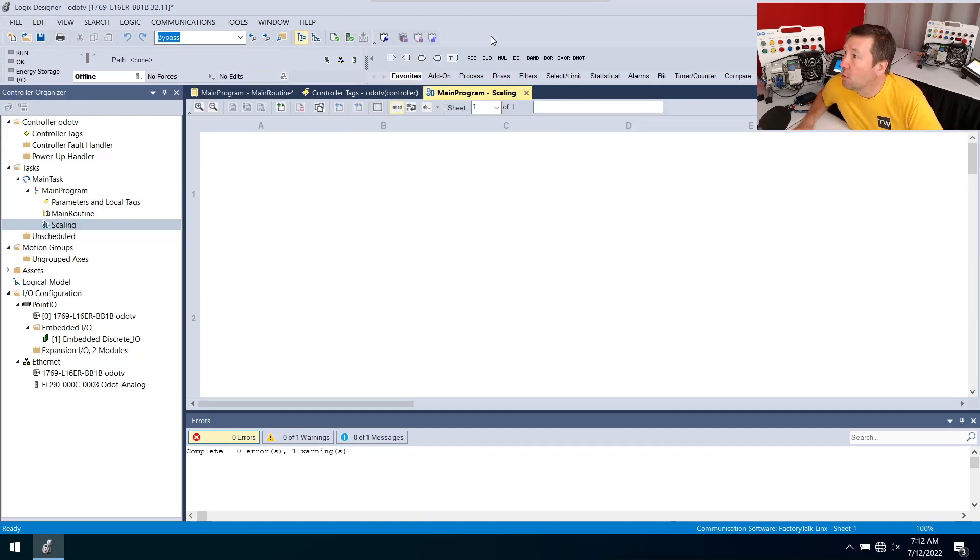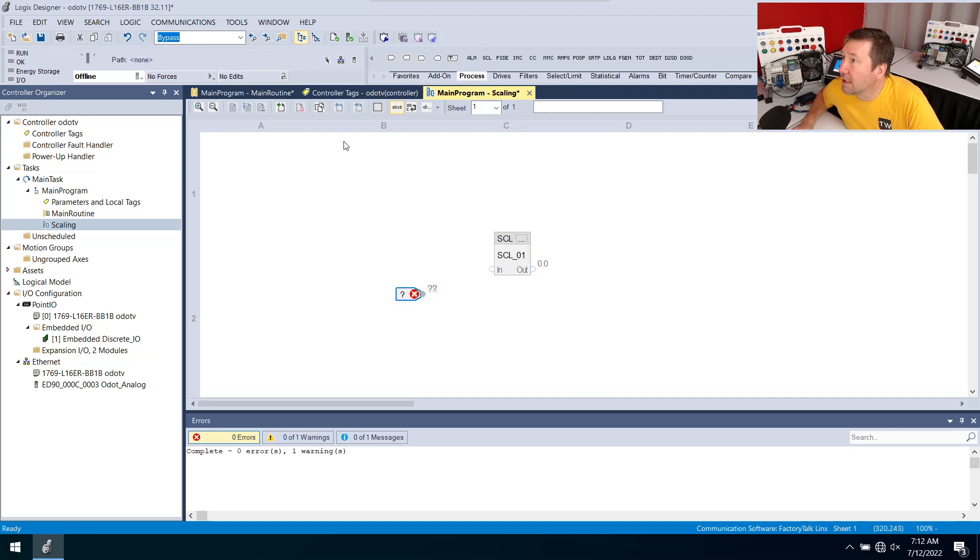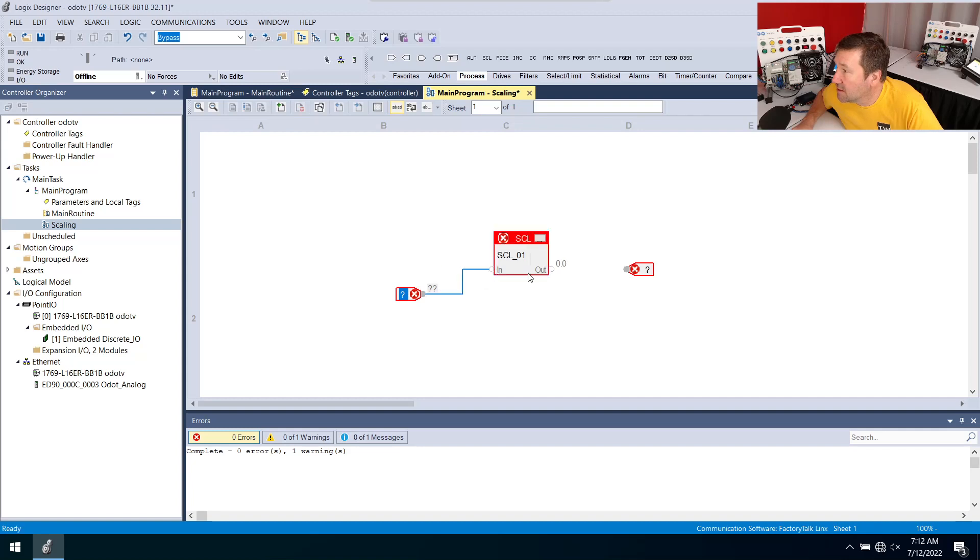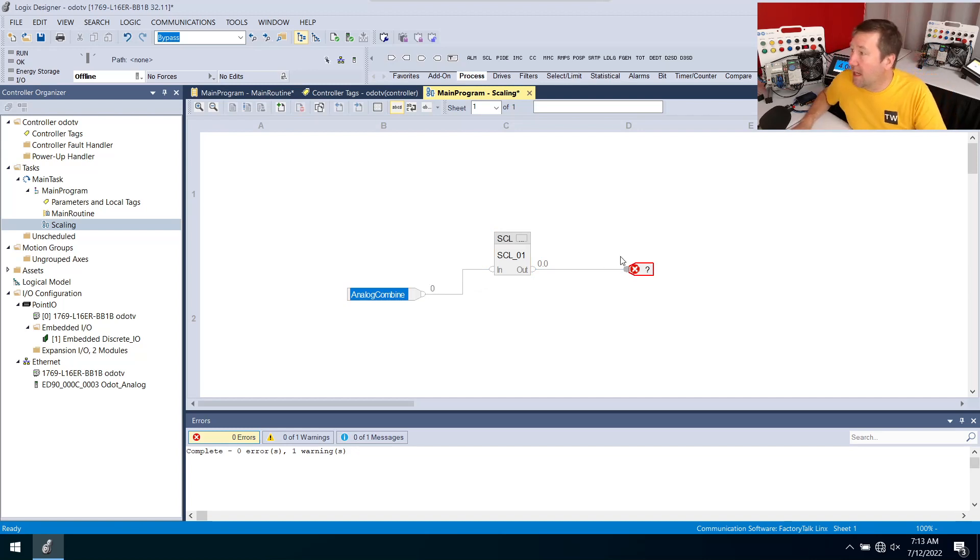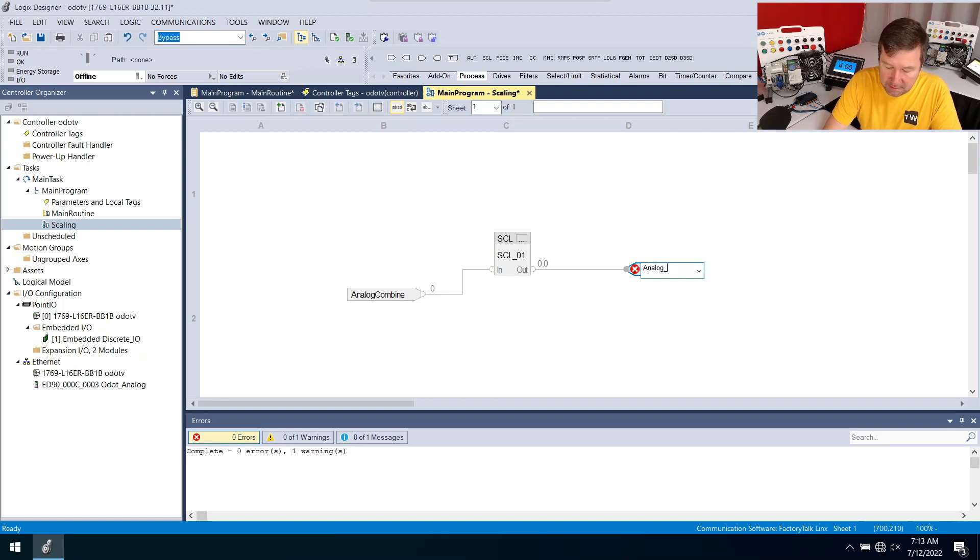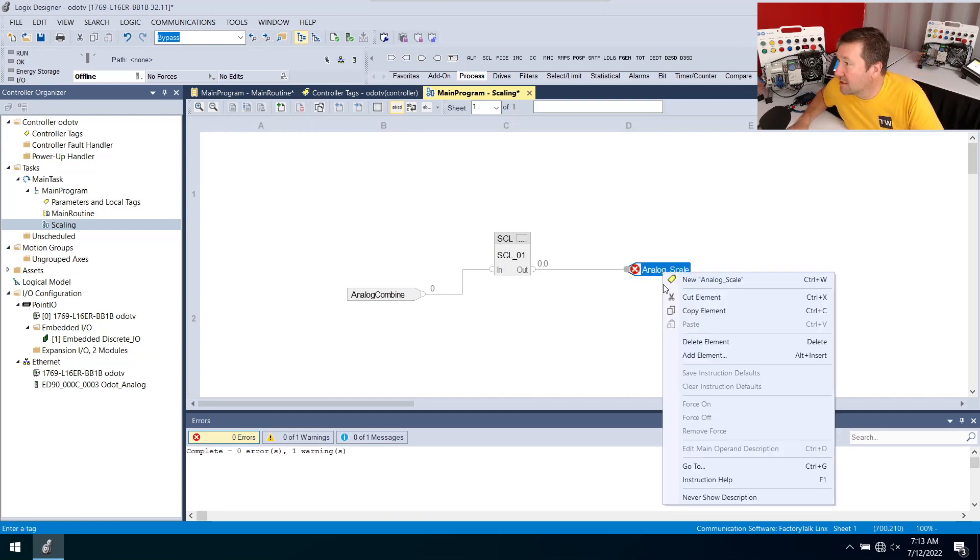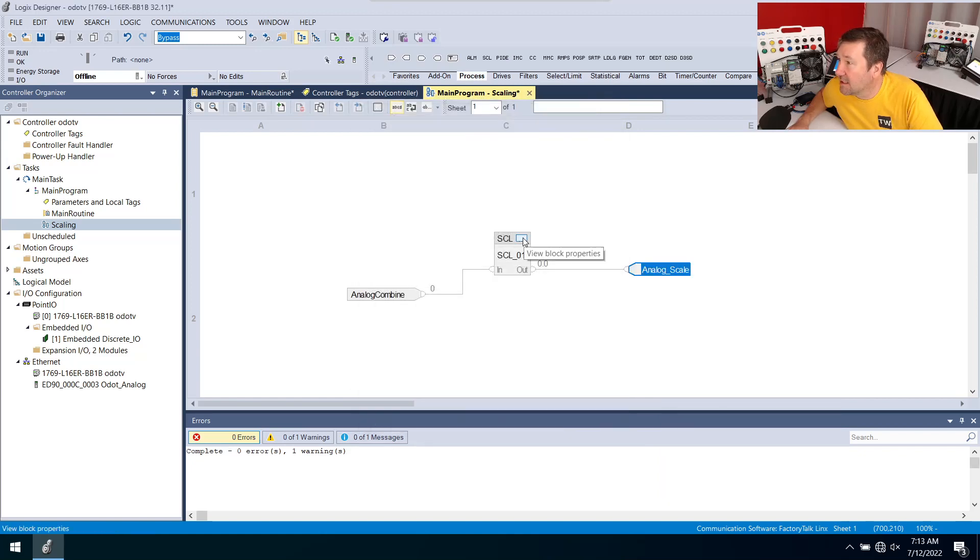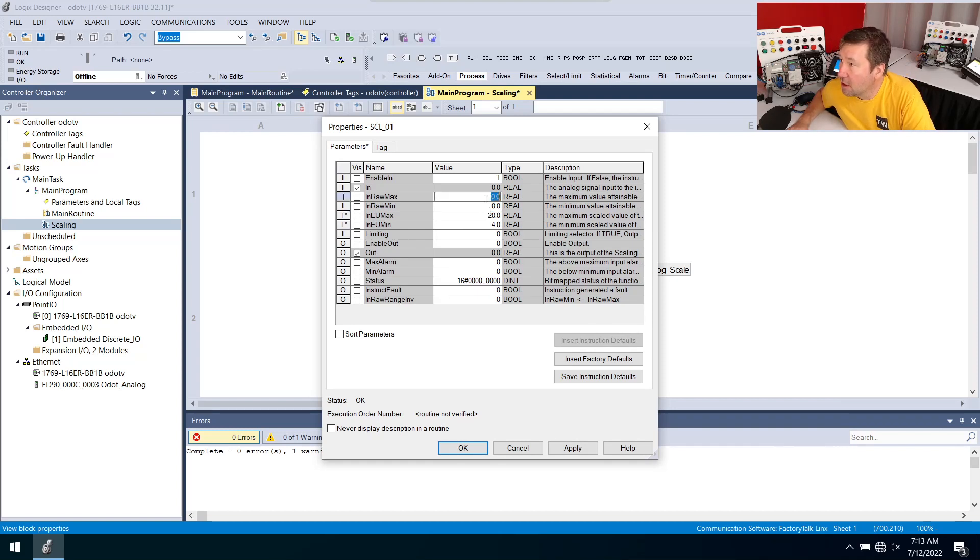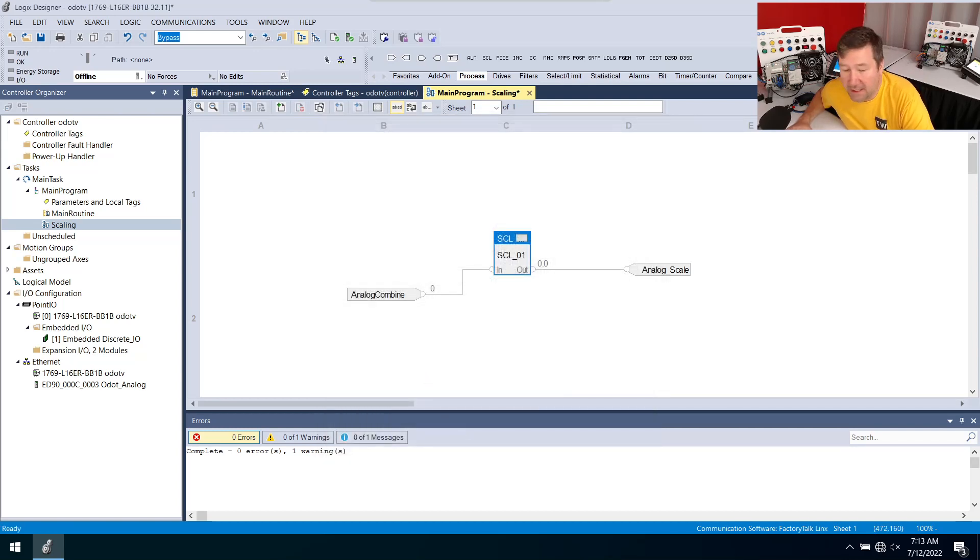Now if we open up that function block we're going to go to our process tab and bring down the SCL instruction and bring down input and an output. We'll put some connectors in here. Our input is going to be that analog combine and our output is going to be analog scale. I'm going to make the analog scale a real number that way we have a decimal place in it. We're going to click the dialog box here and this is going to take our raw units and turn them into our engineering units. My engineering units are going to be four and 20 and then our raw units go from zero to 27648 and we'll click okay.